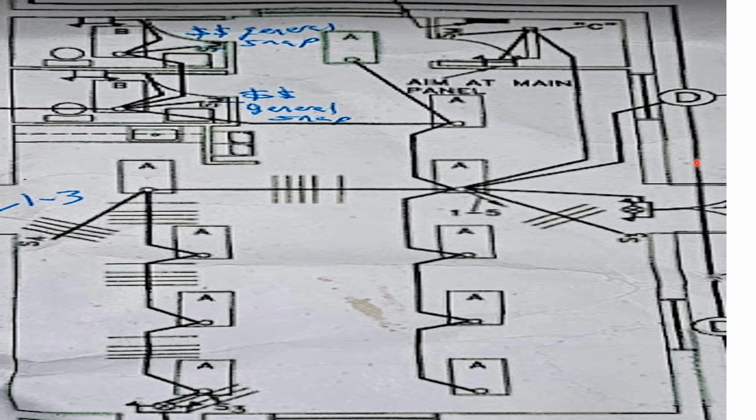Then I need to count my couplings in between. I have 1, 2, 3, 4 couplings. Then I have to come here and do a male connector on this side and a male connector on this side. Then I need to terminate at a 4 square box. That 4 square box is going to need an extension ring or plaster ring, or a regular RS cover, depending on how the finish is.